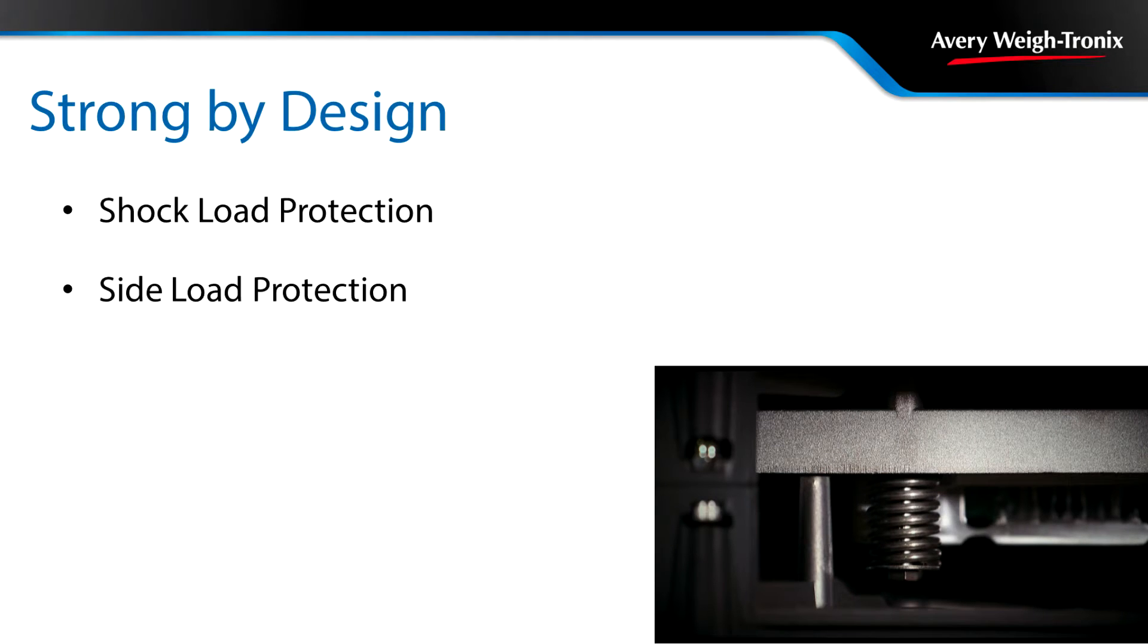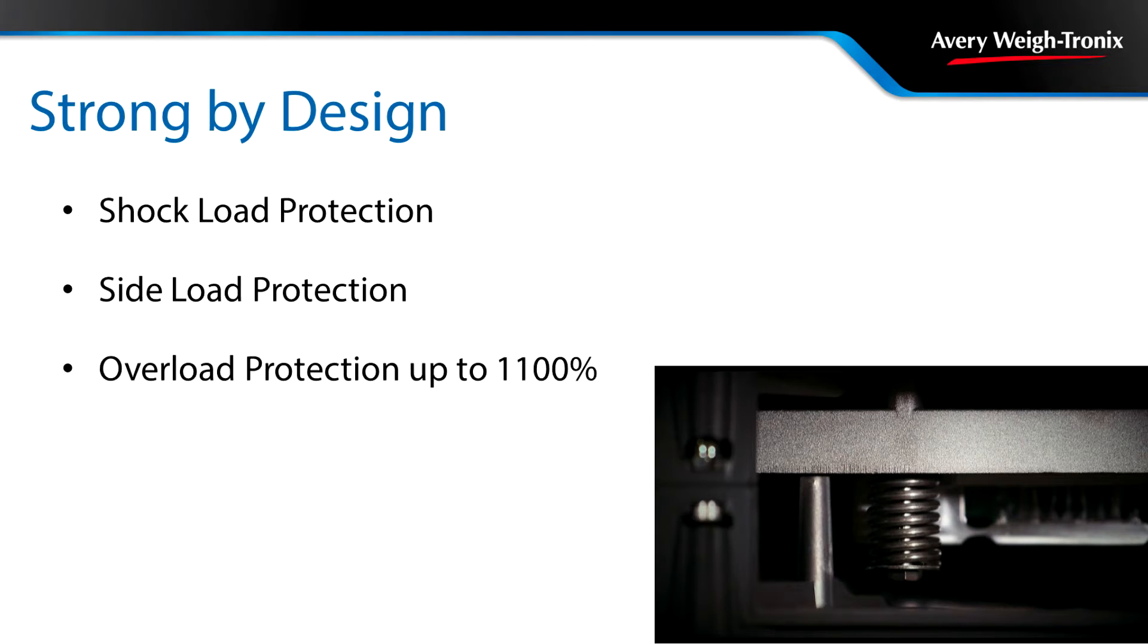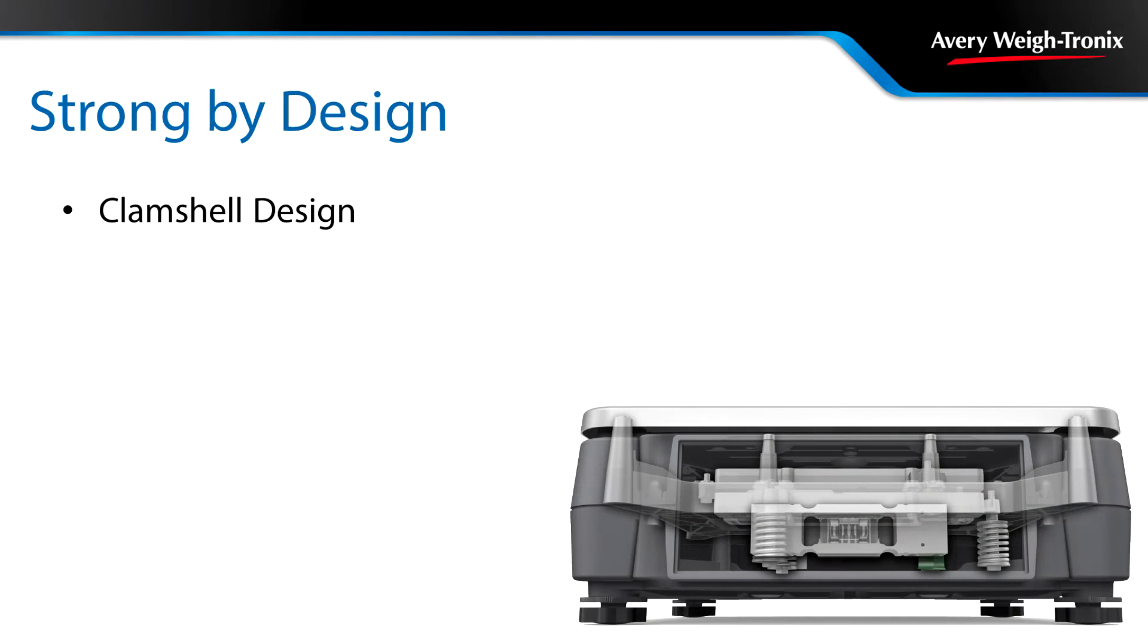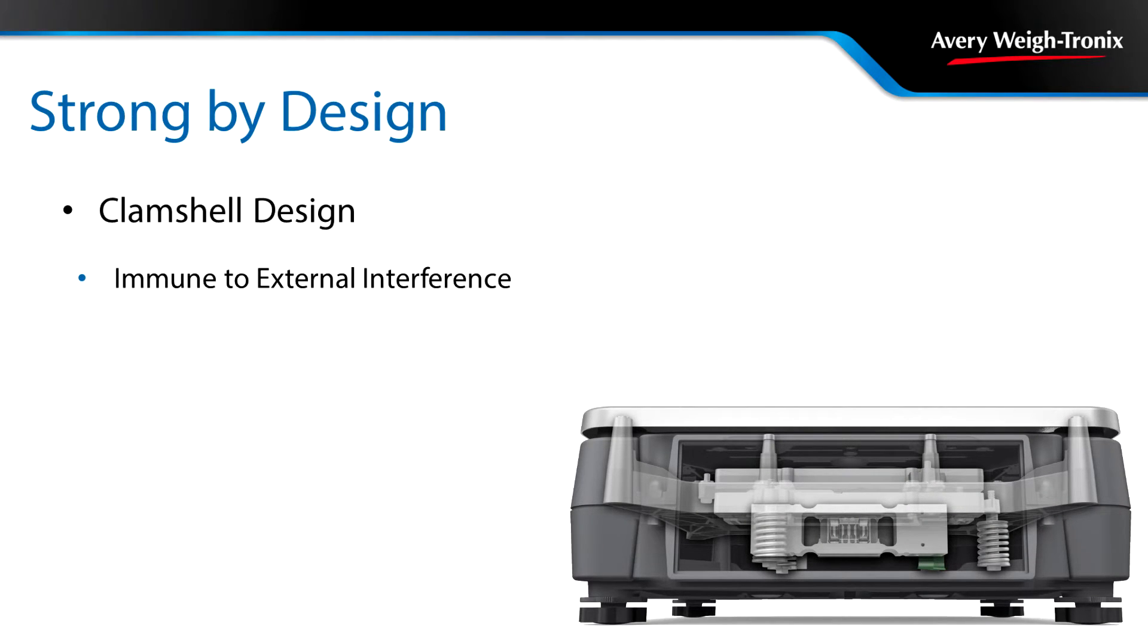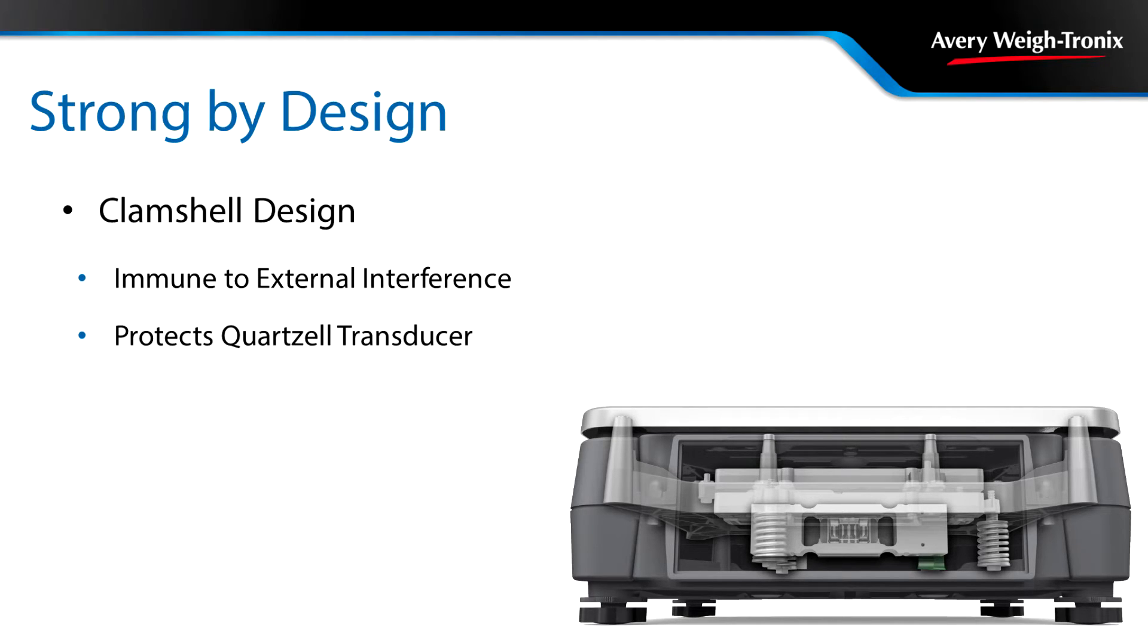The intelligent spring break-away mechanism provides shock and side-load protection as well as overload protection of up to 1100%. The die-cast clamshell design of the robust enclosure isolates the internal components from external noise, protecting the sensitive Quartzell transducer to ensure the accuracy of your component counts or precision weighing.